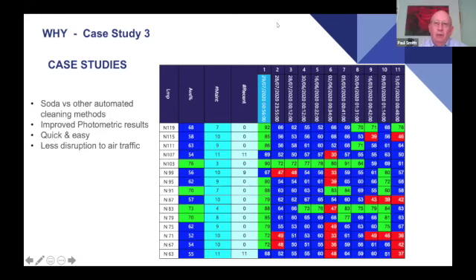Okay. One of the most effective ways of improving your light output, this quite clearly shows, is to simply clean the fitting. No taking the fitting out, no taking it back to the workshop, refurbishing it. Start off with a simple clean, get a good cleaning regime into place, and you can maintain your serviceability level very easily. There's also the time then, Paul, isn't there? Oh yes, it's a very quick operation, using the correct tool for cleaning, as we've demonstrated, and it's environmentally friendly. But the other aspect is if you still adopt the traditional maintenance of taking an inset light fixture out and replacing it with a serviceable one, that in itself brings additional demands, because it's time consuming, and you've got to do other mechanical and electrical functions associated with it.